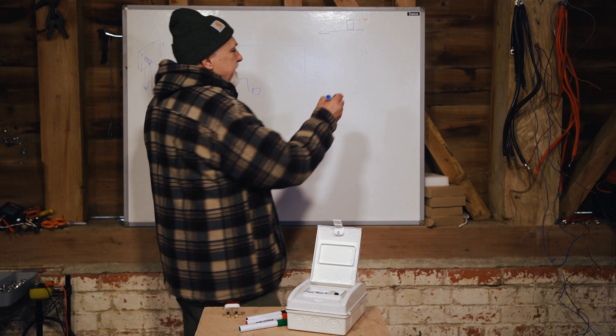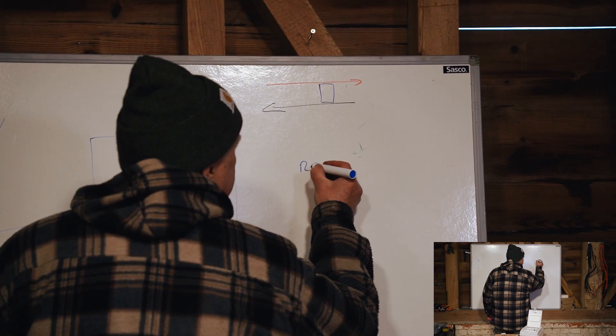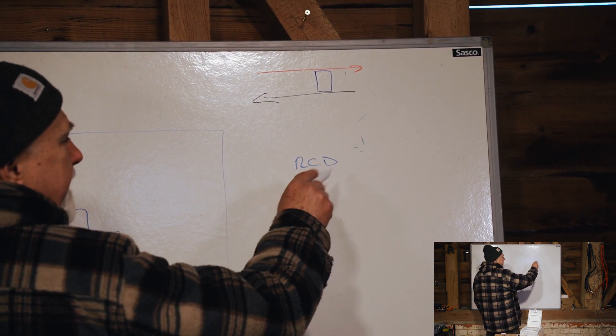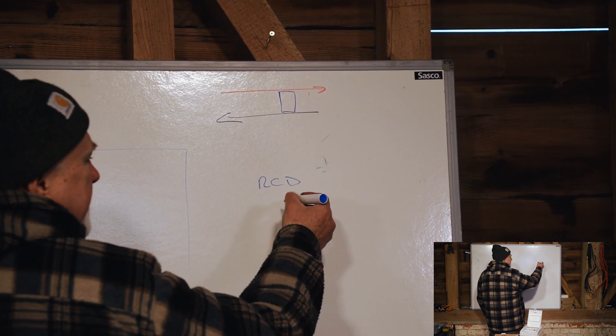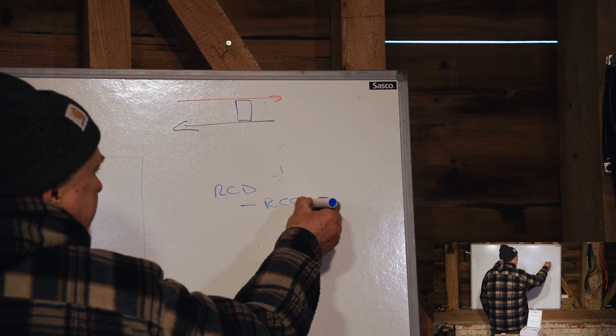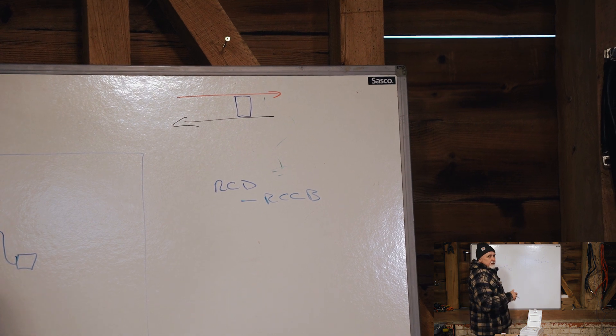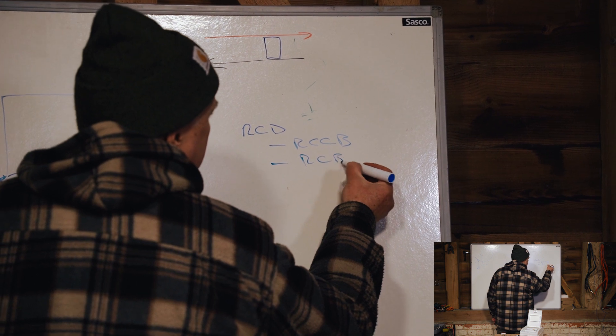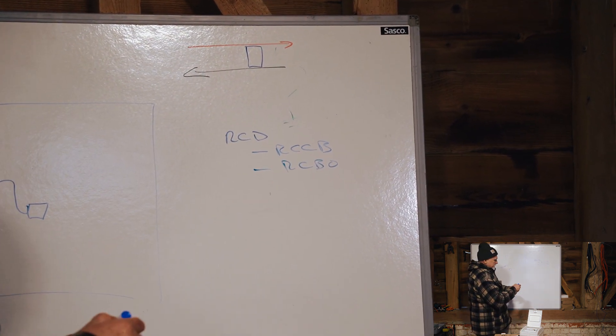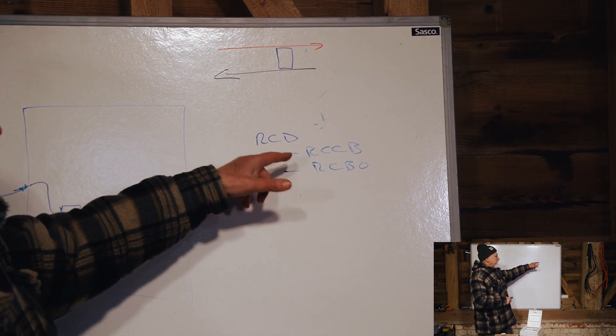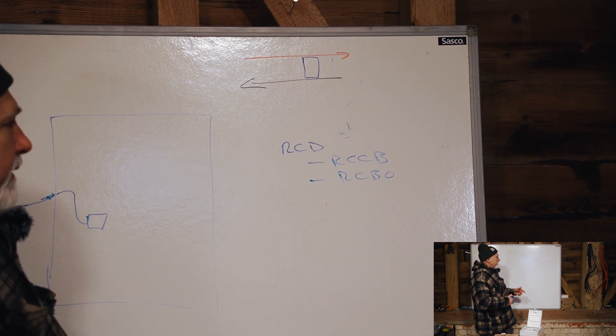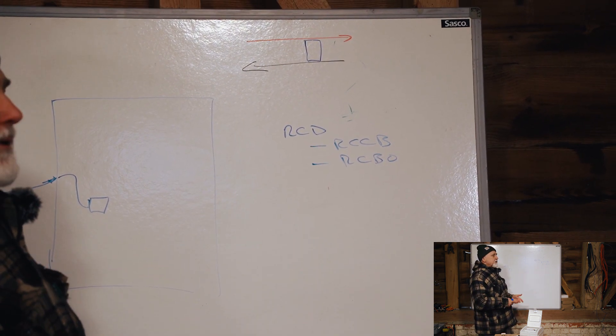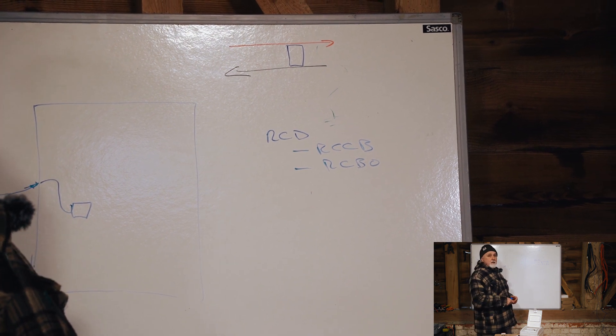And there are essentially, so when we say RCD, we're talking about the family of residual current devices. So it's a family of devices. This is also sometimes known as the RCCB. And this is the most common that we have installed everywhere. But you can have what is called an RCBO. And the difference between these two is that this only protects a leakage to earth, protects from a leakage to earth. And this one protects from a leakage to earth as well as overcurrent and dead shorts and things like that.